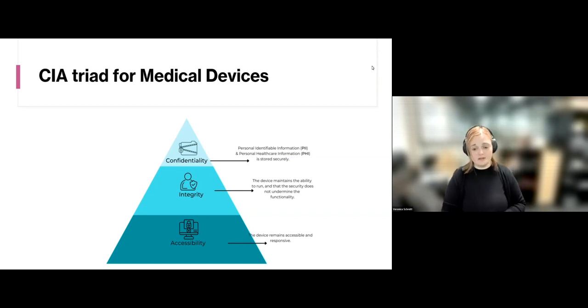The interesting fact most people don't know about these devices is that even when the device is bricked, it will go back to VVI mode, the baseline mode, where it beats at approximately 65 beats per minute. So the device never really switches off unless there's a catastrophic battery failure. It will switch to this mode even when the battery is almost depleted, which means integrity is very important on these devices.